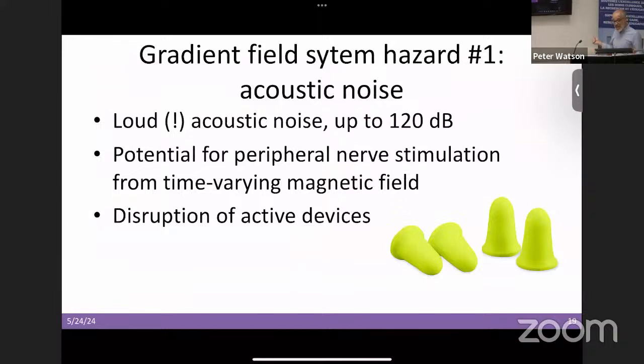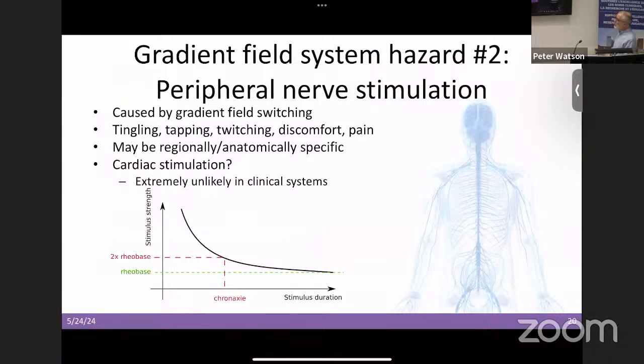Gradient field system's main hazard is potential hurting of your hearing apparatus. Very loud acoustic noise, not to be confused with imaging noise. And so we will put in hearing protection. The second possible hazard is peripheral nerve stimulation, which is a temporary stimulus. It's caused by gradient field switching. This can go from a tiny tingling sensation up to a tapping and even discomfort or painful stimulus. It's usually anatomically specific, and it's usually limited well below anything that would cause cardiac stimulation.